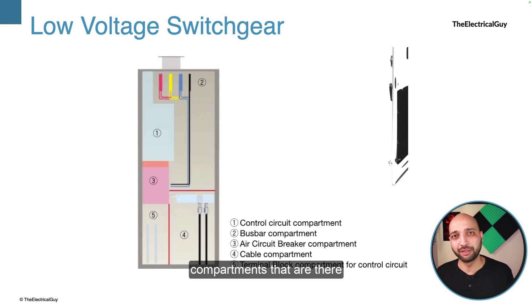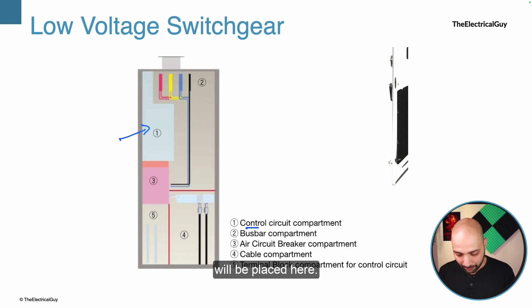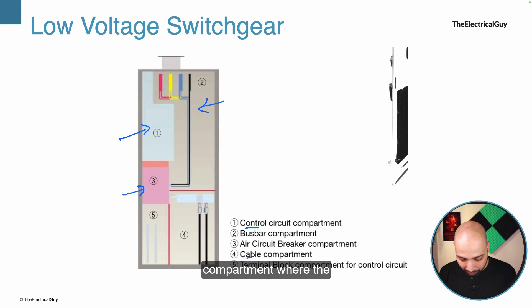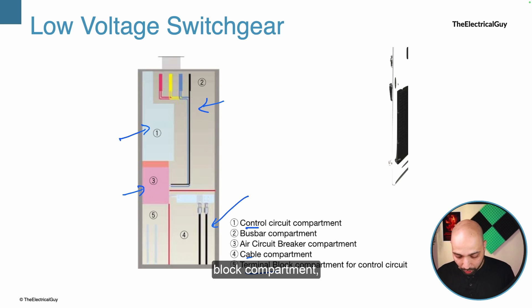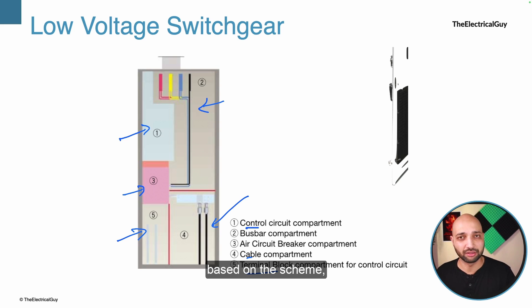The general compartments in a low voltage switchgear panel are: the control circuitry compartment containing switches, MCBs, contactors, and relays; the bus bar compartment where cables enter and the bus bar runs through all panels; the air circuit breaker compartment where the circuit breakers are placed; the cable compartment where incoming cables — say from a transformer — enter; and the terminal block compartment for remote indications via wiring. This is a general overview and the arrangement may vary based on the scheme and the manufacturer.